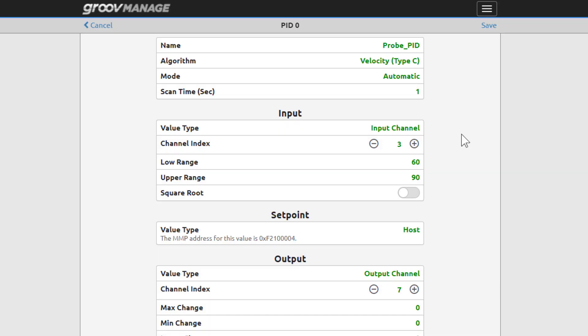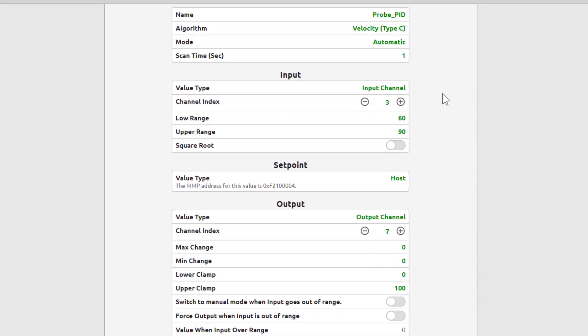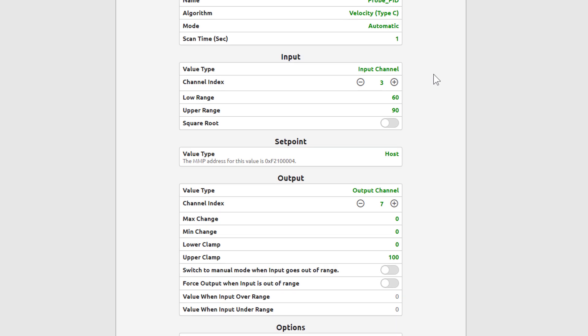Designate the input channel here. In our case, it's channel 3 with the ICTD probe. You can set up low and high range limits. In this case, it's not expected the room temperature will be under 60 or over 90 degrees. Square root isn't selected. It's used when you want the error calculated based on the square root of the input, such as in some flow control systems.